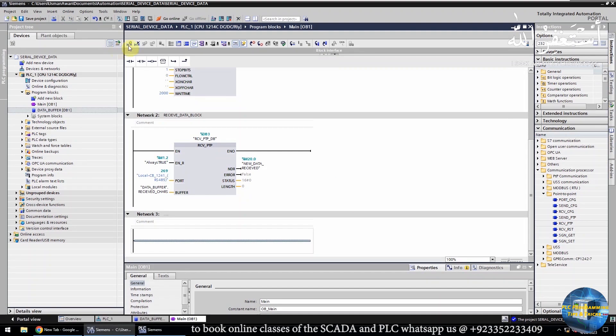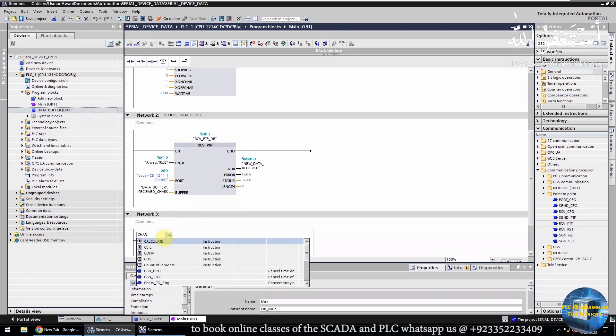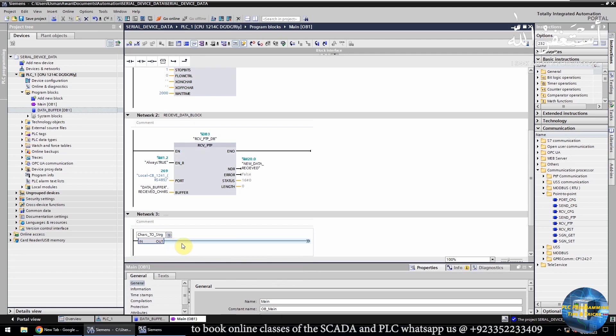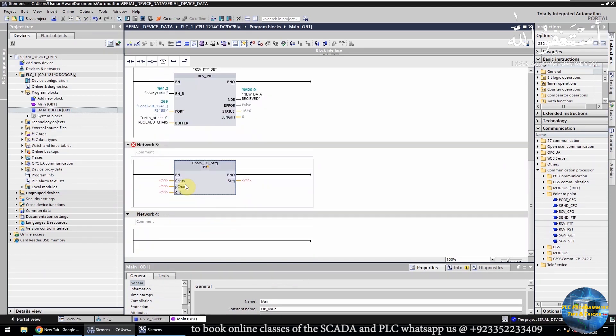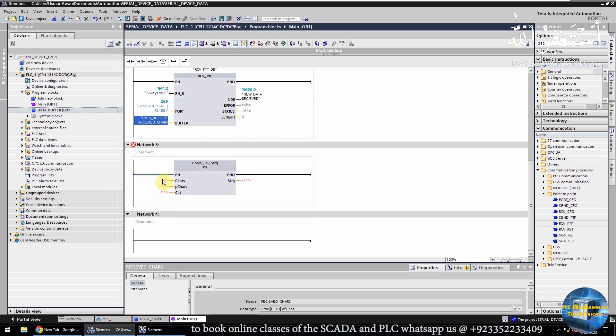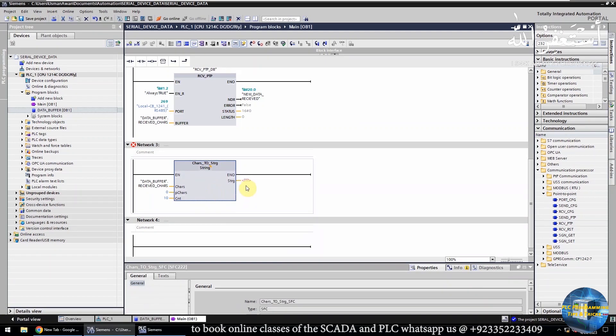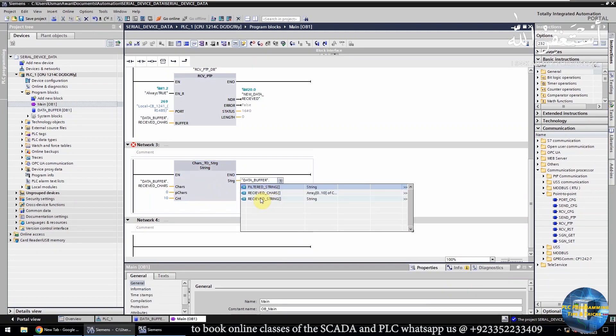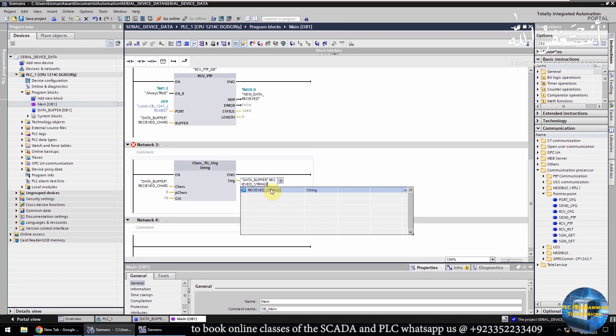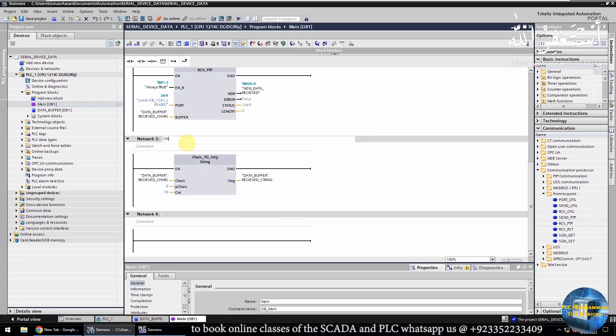In network 3, we will convert the received characters array to a string of characters. We will drag and drop the char-to-string function on the ladder. Enter the data buffer array at the chars input. Next, we will enter 10 in the count input, which means the string will be created from the first 10 characters in the buffer array. We will then assign the data buffer received string at the output of this function, which will store the output string there.